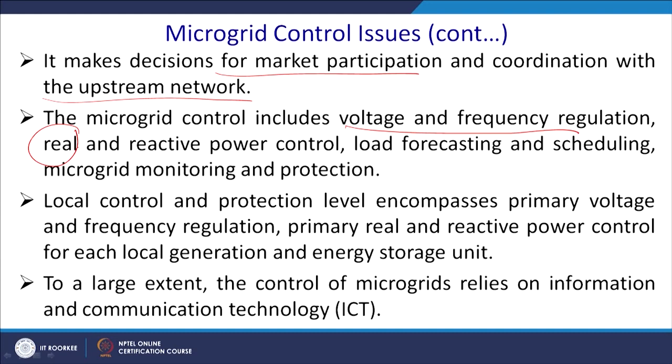Microgrid control includes voltage and frequency regulation. If you are willing to sell power, you are not allowed to sell at different voltages and frequencies — it has to match the grid frequency and desired power factor. For this reason, you require real and reactive power control, load forecasting to know where the peak load will come, load scheduling to shift load where you have excess generation, and microgrid monitoring at both the physical and sensor levels, followed by protections for faults and different aspects.